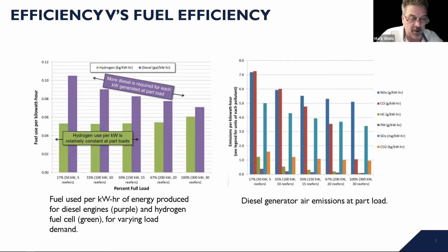The report basically confirmed that historically, the DGs used to power these reefers were on average only operating at 30% or part load. And as a result of using fuel cells, they were able to reduce emissions by 35%. It also provided avenues and approaches for how this could be widened for further adoption with other uses in the same marine port. The graph on the left shows the results of some of the tests where the fuel cell was used to power reefers. What this illustrates is the amount of fuel burned per kilowatt hour, in this case hydrogen, compared to the equivalent amount using a diesel generator.